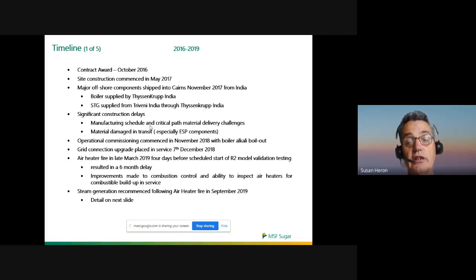Operational commissioning commenced in November 2018, so we didn't come close to making the practical completion date of July 8, 2018, with the boiler alkali boil-out being the first step in cleaning up all the starting systems. The grid connection upgrade was placed in service basically in early December. We were able to commence the alkali boil-out powered from the original 7 megawatt lower pressure boiler from a power source point of view.